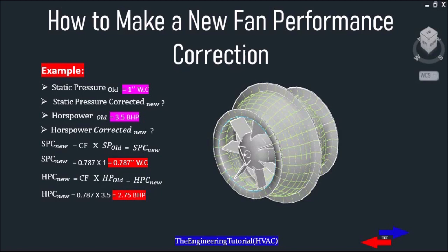Static pressure corrected new equals the correction factor multiplied by static pressure old: 0.787 × 1 = 0.787 inches of water column. Horsepower corrected new equals the correction factor times horsepower old: 0.787 × 3.5 = 2.75 brake horsepower.